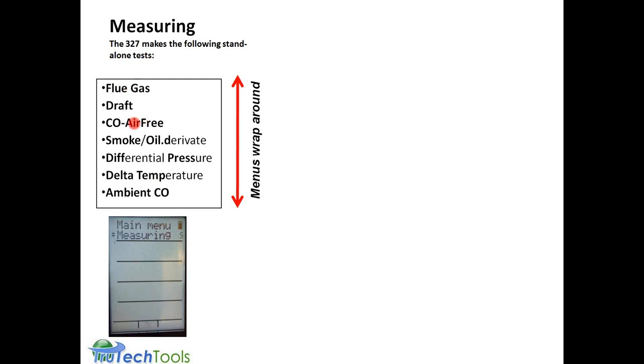Every time you take a test, it's stored in a temporary notebook type file, which could then be printed out with the combustion record, since you will have a difference, hopefully, between the ambient CO, the CO air-free, and the flue gas or the stack gas CO. They will all be different numbers, but you need to have them labeled to make it a very comprehensive report. And again, they'll either come back up in the meter before an on-off cycle, or you could print them out.